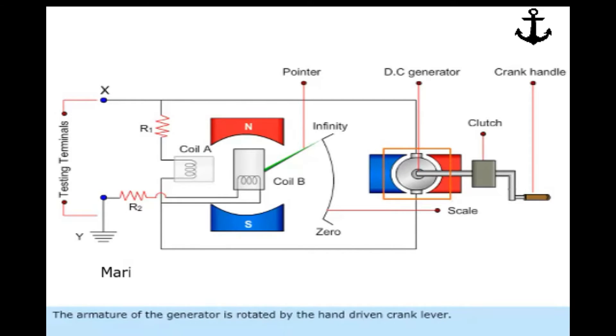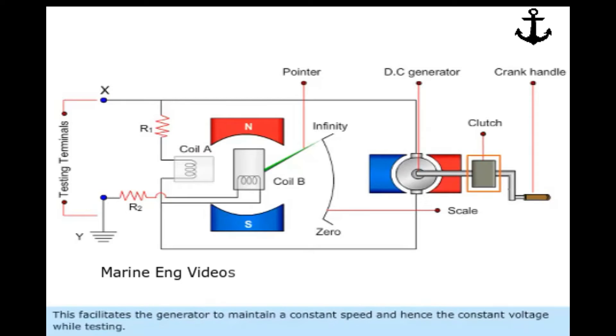The armature of the generator is rotated by the hand-driven crank lever. The clutch mechanism is designed to slip at a predetermined speed. This facilitates the generator to maintain a constant speed and hence constant voltage while testing.